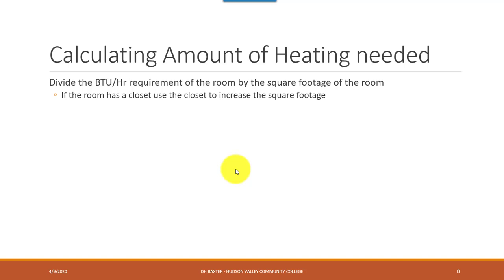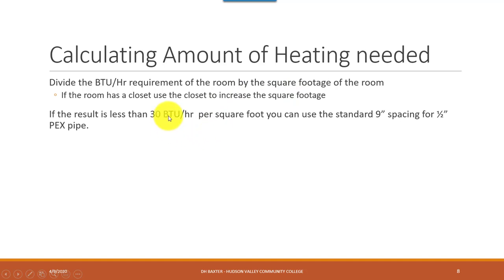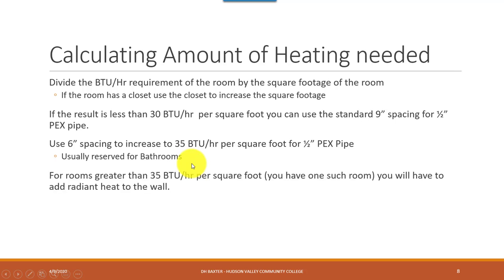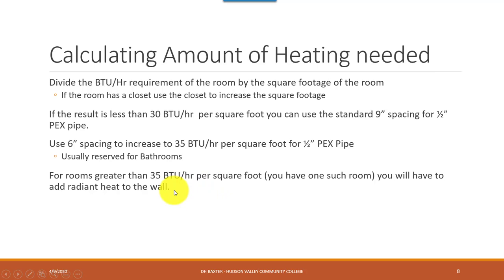Here's the question: you've only got so much spacing on the floor. You can go nine inches, or in a pinch drop down to six-inch spacing with half-inch pipe. To check if that's enough, divide the BTU requirement of the room by the square footage, and that tells you BTU per hour per square foot. You can also use closet space to increase allowable square footage. If the result is less than 30 BTU per hour per square foot, standard nine-inch spacing for half-inch PEX will work. Six-inch spacing gets you up to about 35. If the number is greater than 35, you'll need to add radiant heat to the wall as well.